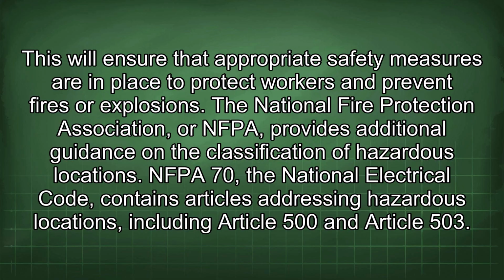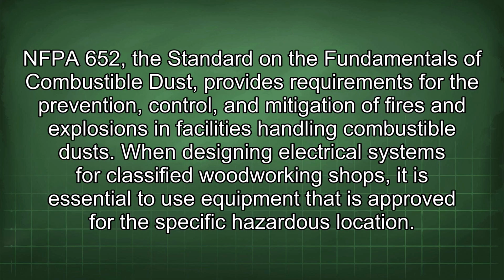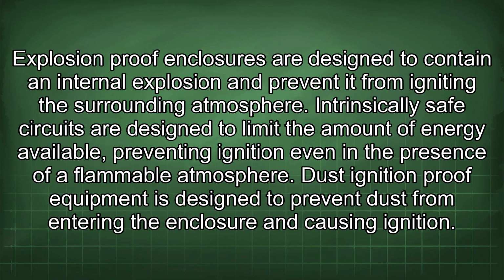The National Fire Protection Association, or NFPA, provides additional guidance on the classification of hazardous locations. NFPA 70, the National Electrical Code, contains articles addressing hazardous locations, including Article 500 and Article 503. NFPA 652, the Standard on the Fundamentals of Combustible Dust, provides requirements for the prevention, control, and mitigation of fires and explosions in facilities handling combustible dusts. When designing electrical systems for classified woodworking shops, it is essential to use equipment that is approved for the specific hazardous location. Explosion-proof enclosures are designed to contain an internal explosion and prevent it from igniting the surrounding atmosphere. Intrinsically safe circuits are designed to limit the amount of energy available, preventing ignition even in the presence of a flammable atmosphere. Dust ignition-proof equipment is designed to prevent dust from entering the enclosure and causing ignition.